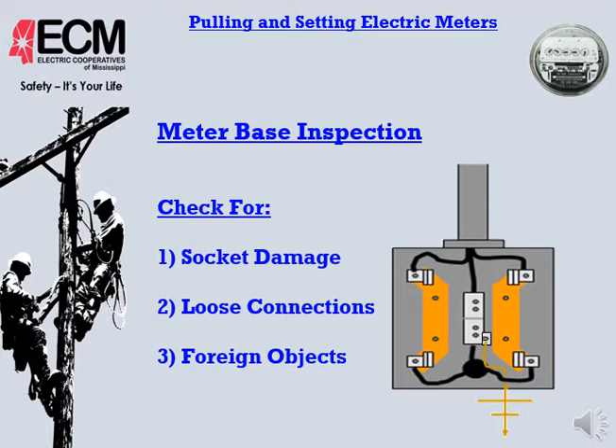The next thing you know, it generates more heat, and eventually it will cause a problem where there's no question where it was located. A loose connection also causes insulation damage on the copper wires where they come into the lugs, source, or load. Usually you'll find the insulation on that copper wire has been hot and melted, maybe even peeled back, exposing the copper strands, and those strands could have a color change from their original color at installation.